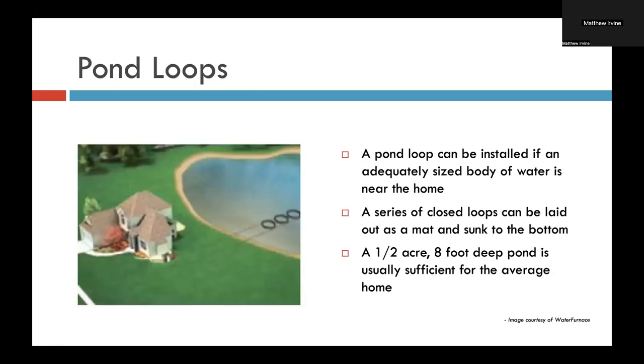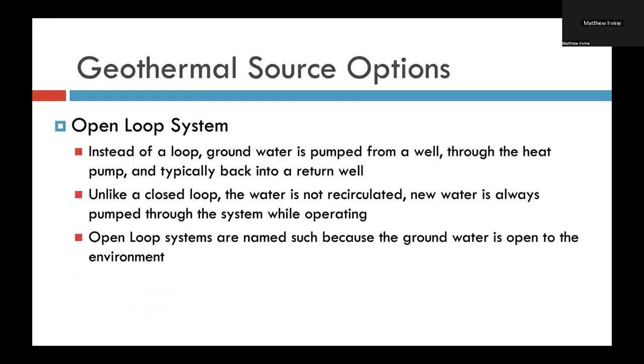Next. A pond loop is one that is installed if there's an adequately sized body of water near the home. Basically, a series of closed loops can be laid out as a mat and sunk to the bottom. So shorter lengths of pipe, more densely packed than a horizontal loop. But for approximate purposes, residentially, you're going to want a pond that's about a half acre and 8 foot deep as a minimum. Deeper is fine, larger is fine, but you do need sufficient depth and surface area to rely on that body of water as your energy source. Next.